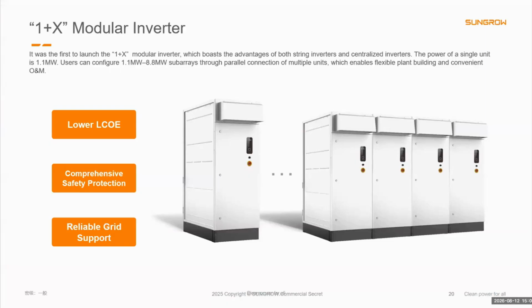Now let's move to the 1 plus X modular inverter. Each unit is 1.1 megawatts, and multiple units can be connected in parallel to create subarrays from 1.1 to 8.8 megawatts. The concept combines modularity and redundancy with the system economics of large, centralized solutions. Its three main values are lower LCOE, comprehensive safety, and reliable grid support.